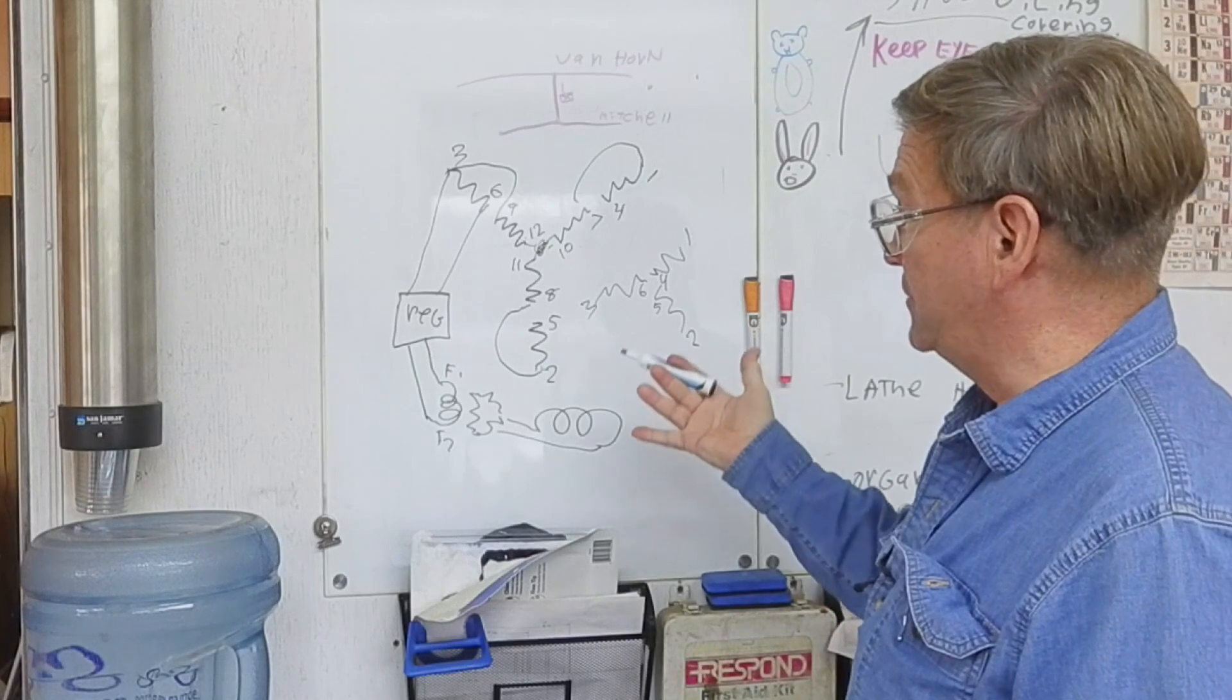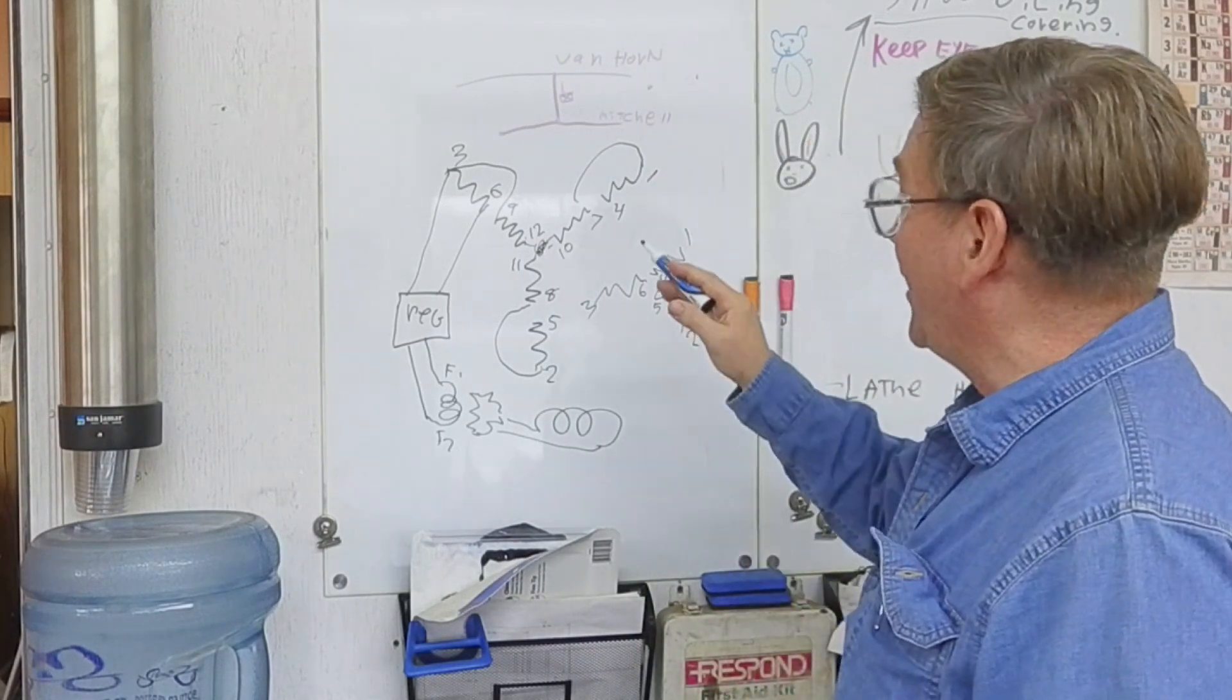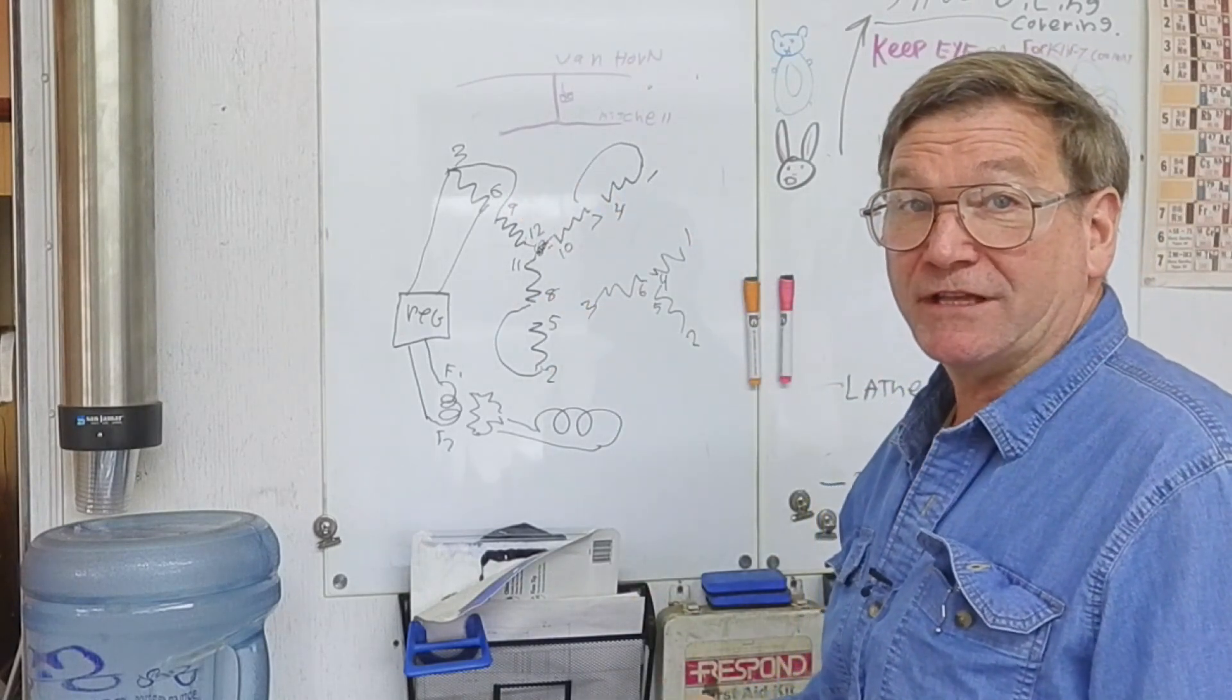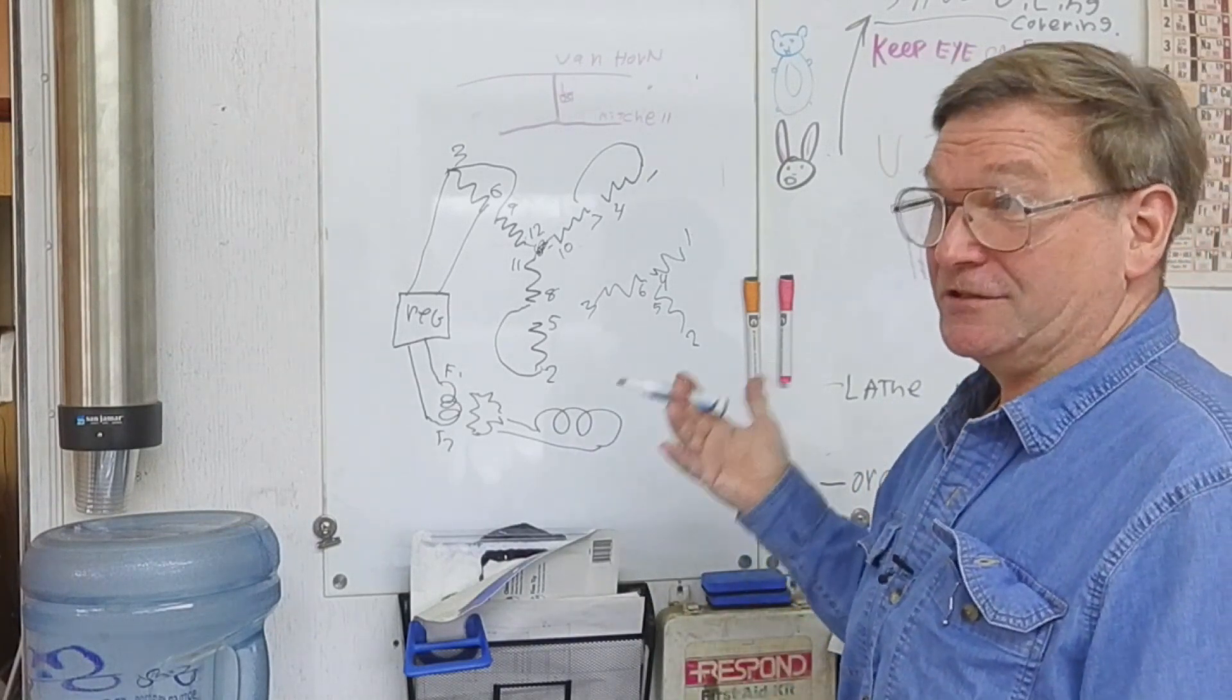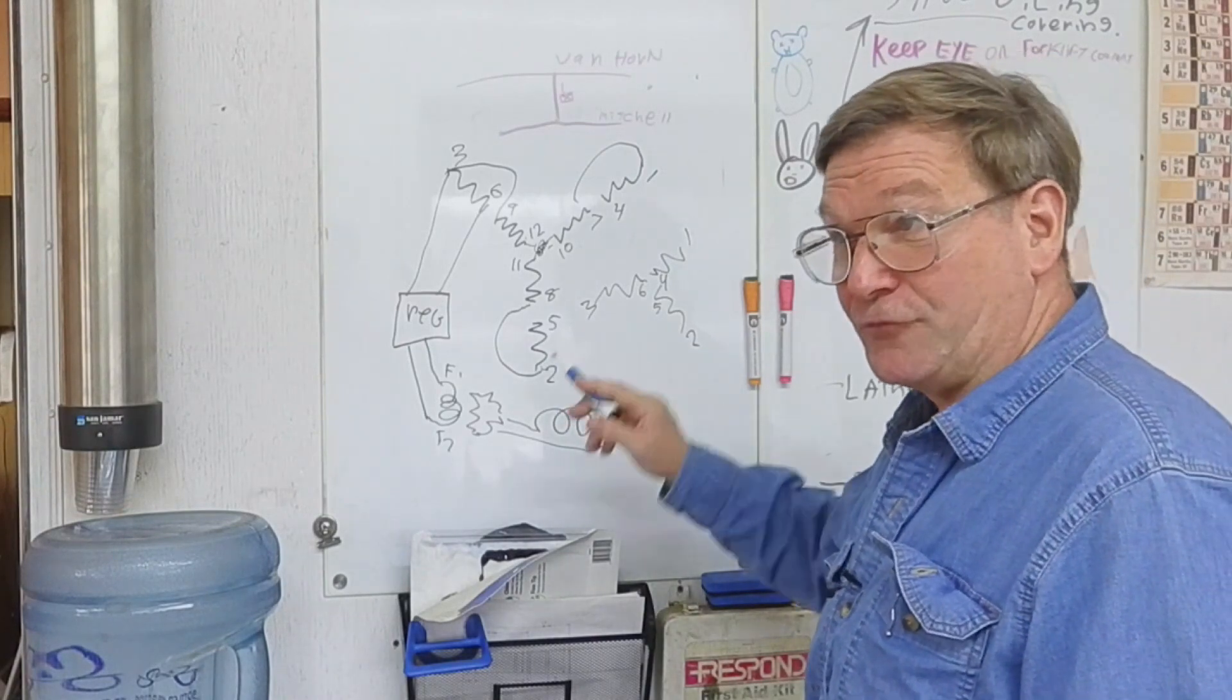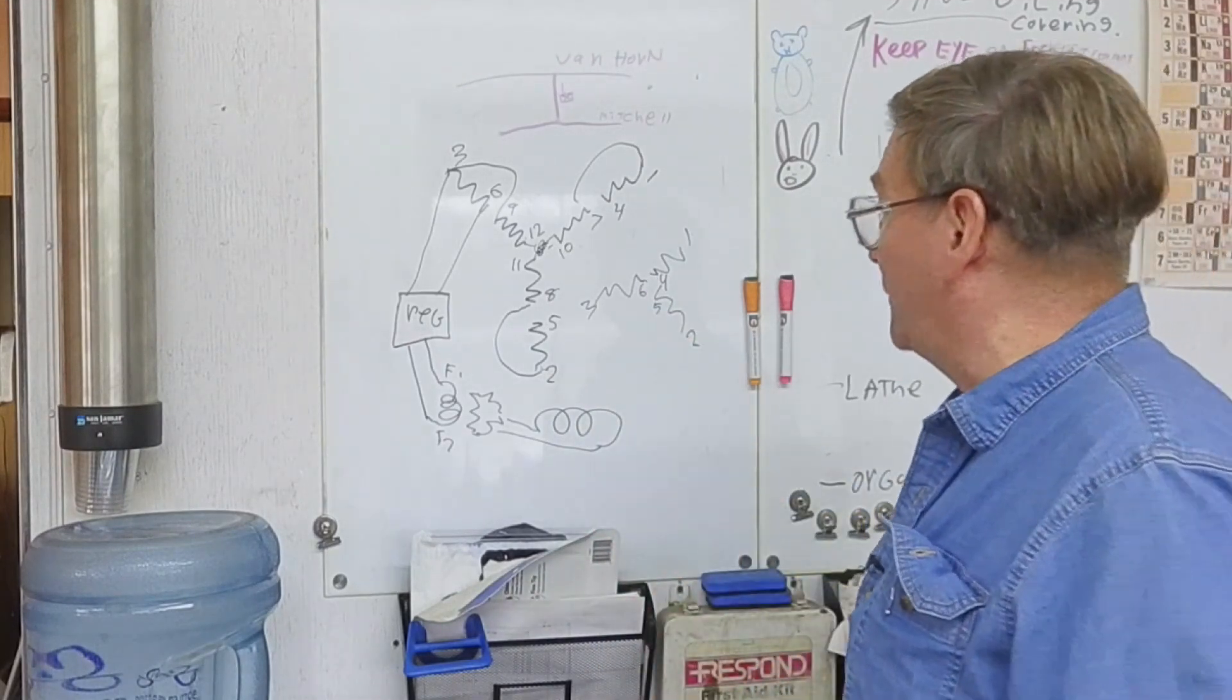Normally, there's other ways you can connect this. You can also connect 240 volt by doing a delta. We're not going to explain that right now. But the big difference on most generators you're working with, most of them today are wired in a Y, which is this is the Y configuration. And your difference between putting out 208 and 240 is usually where you set the regulator. Same as for the 480, you could have your 480 would do 480. It'll do 460. It'll do 416, as long as your regulator allows you to drop down that far. And you'll have different outputs from all of those.